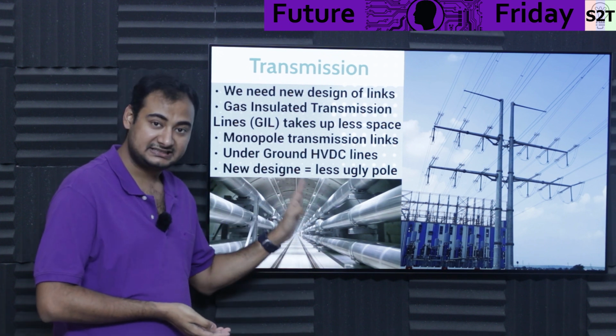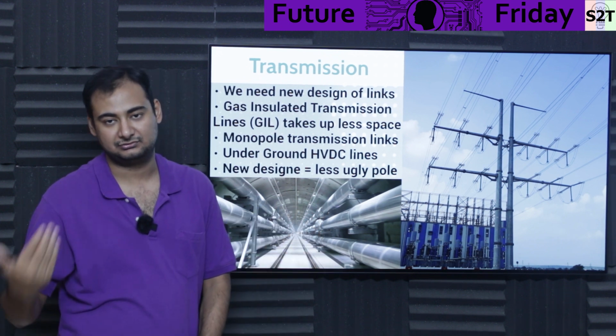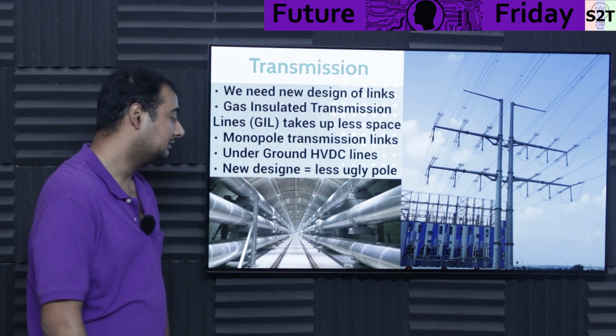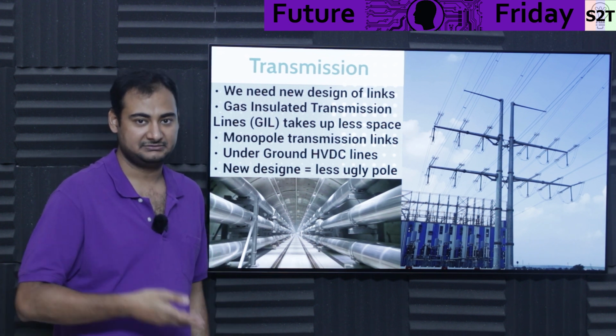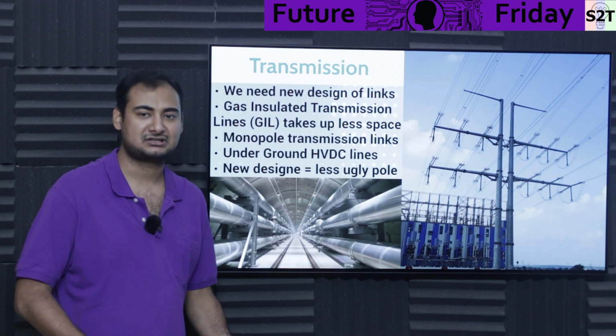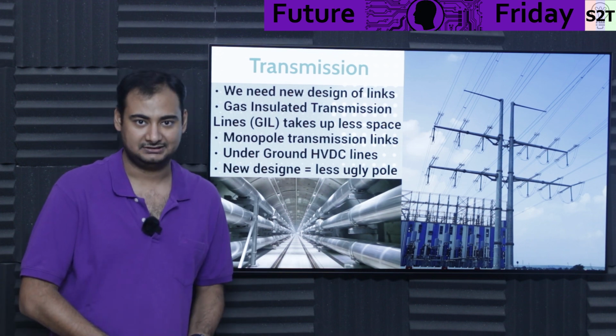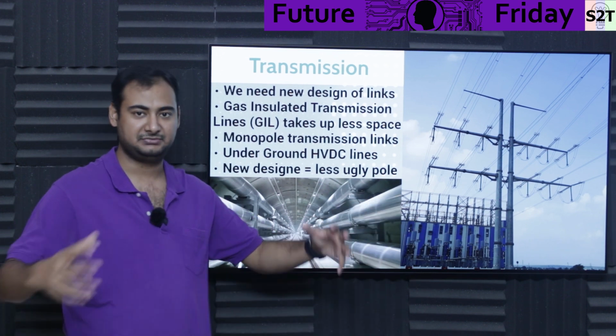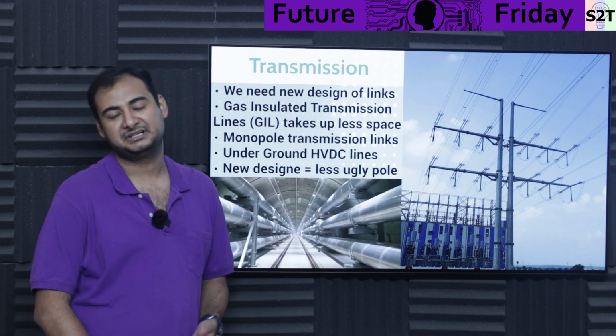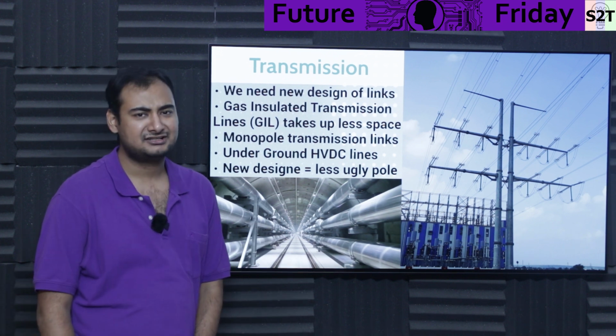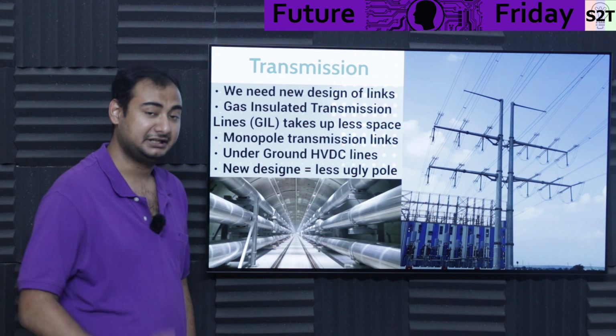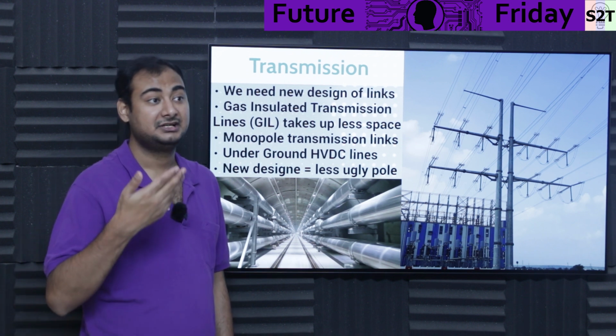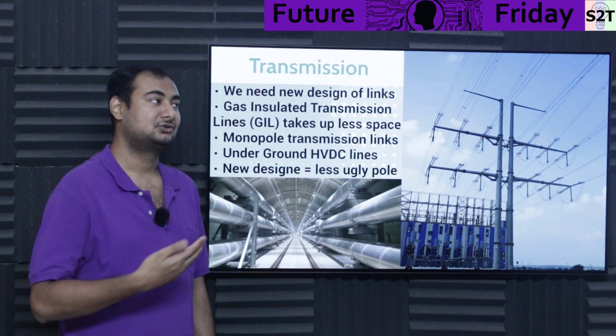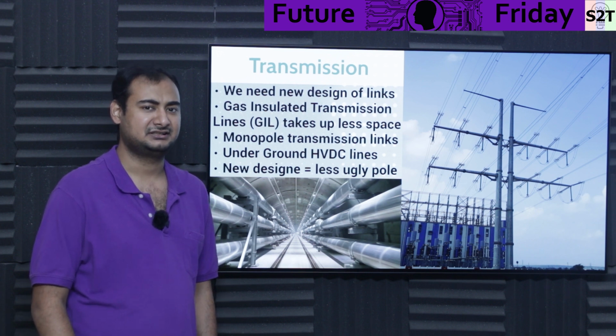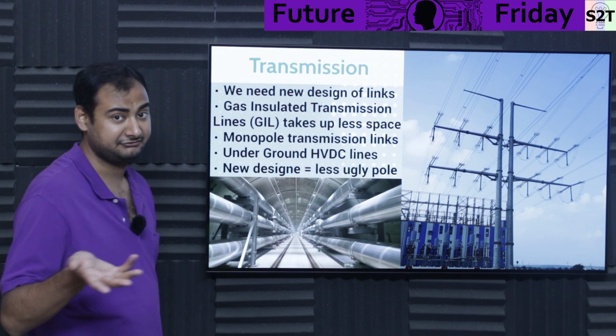You can take the same connection principle and apply it to HVDC to get more power, or use AC if you prefer, because an HVDC converter station isn't something you want everywhere. It makes sense for gigawatt scale, but for megawatt scale it's not really viable. Some companies have reduced costs so much that the smallest unit I've seen is 30 megawatts, so it can be done if needed.